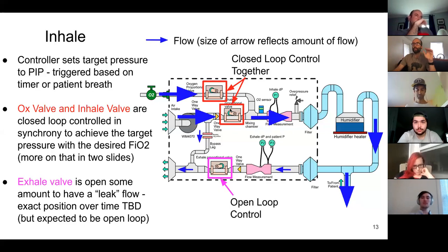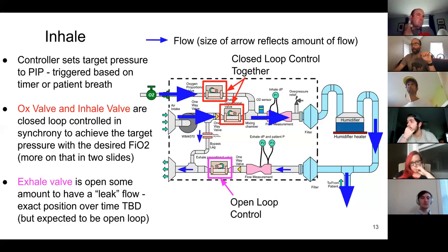So then both of these valves swing together, right? To mix air and oxygen, both valves are going to open a little bit, and that's going to let air flow in. At some point this valve might be closed, especially if we're at 100% oxygen. If this valve is totally closed, then we want some place for the air to escape, so you're not just running the fan against deadhead. Those two flows are going to mix in the piping. Essentially, we don't have an additional oxygen blender or anything to get finer mixing. Then it goes through the venturi, which is what is going to return flow. It's going to go past the overpressure relief valve, which is essentially preventing the patient from seeing pressure above a certain point. It's going to go through all the piping and get to the patient.